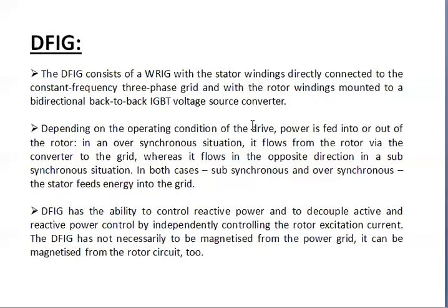So the term doubly fed refers to the fact that the voltage on the stator is applied from the grid and the voltage on the rotor is induced by the power converter. That means this system allows variable speed operation over a large but restricted range. The converter compensates the difference between mechanical and electrical frequency by injecting a rotor current with a variable frequency.